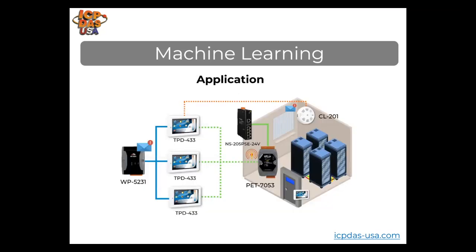In this application, a large data center has a WinPAC running .NET programs in different rooms, along with TPD-433 touch screen controllers, NS-205 PSE-24V Power over Ethernet switches, and PET-7053 digital input modules powered over Ethernet. The WinPAC is connected to many TPD-433 units showing the status of equipment. The digital input module helps detect when equipment is off and shows the status on the door. The TPD-433 passes information back to the WinPAC, which sends email alarms to personnel so they can get equipment back online.